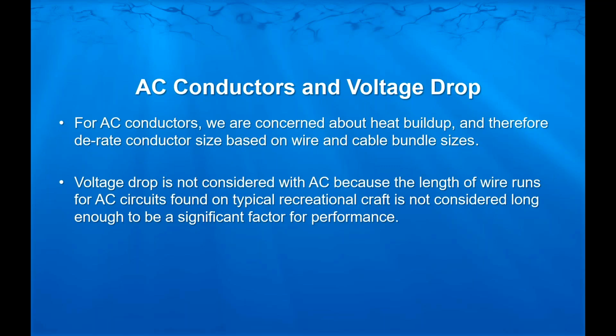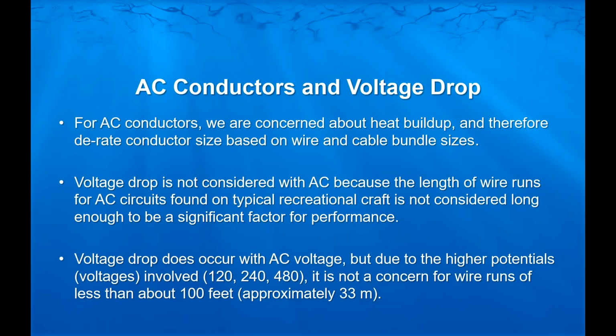In our applications, voltage drop is not considered with AC because the length of the wire runs for AC circuits found on typical boats is not considered long enough to be a significant factor for performance. It does occur with AC voltage over much longer distances, but due to the higher potential voltages that we're dealing with, 120, 240, even 480, it is not a concern for wire runs of less than 100 feet. So anytime you hear voltage drop, in our world, the marine world, you're talking about DC cabling.